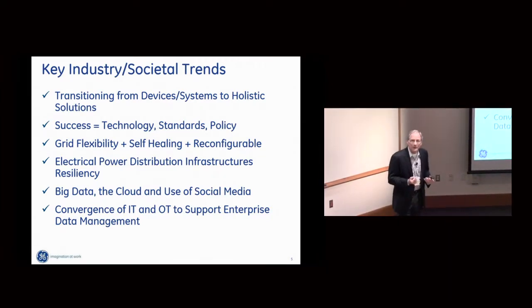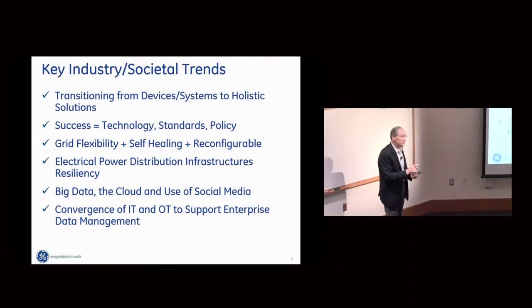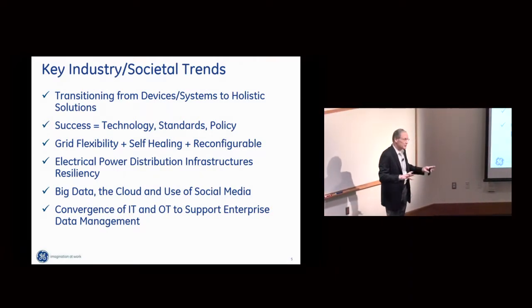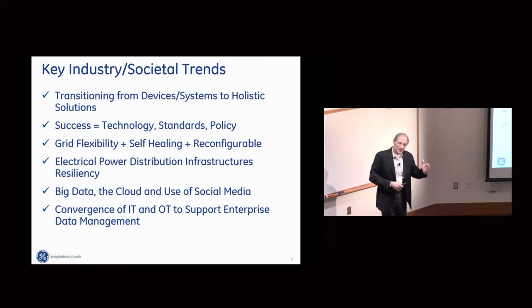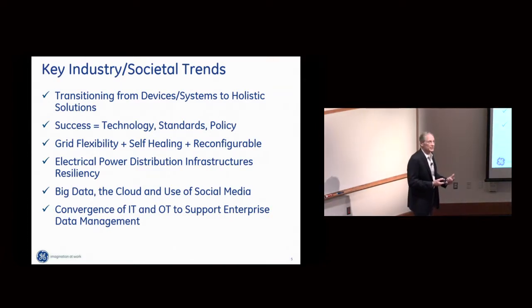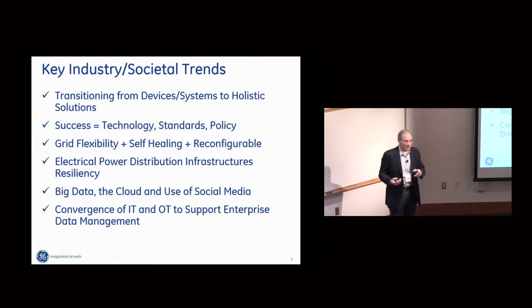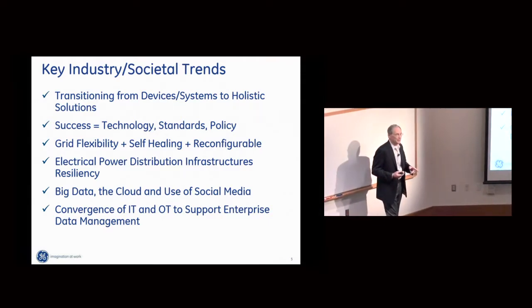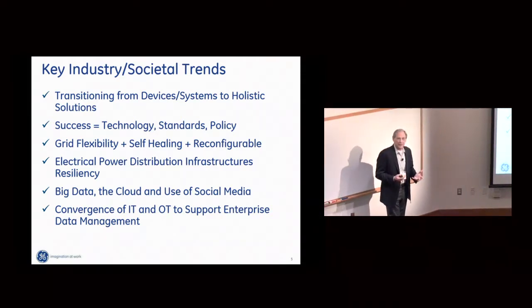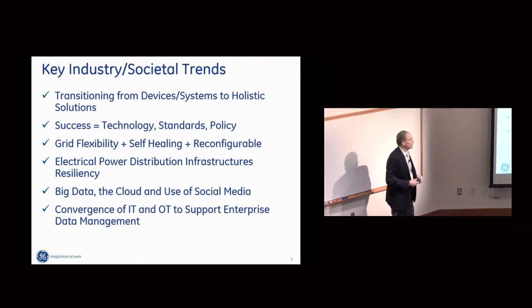We can take the human out of the loop. Many utilities want a human in the loop with downstream restoration because it can be much more complex. But if we keep a human in the loop, we typically exceed the 5-minute threshold for SAIDI and SAIFI, so the customers on the healthy sections of the feeders count against us with reliability.